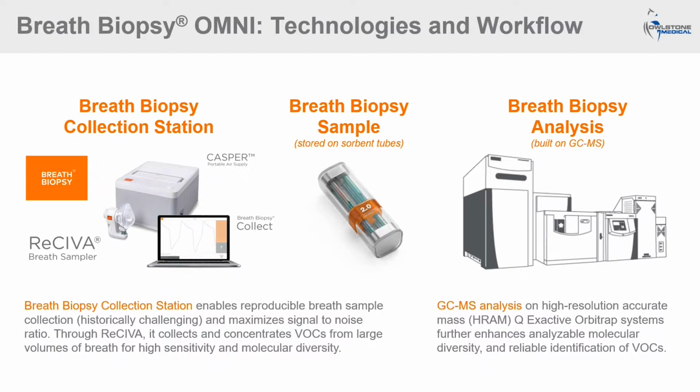Important to that whole setup is also the CASPER portable air supply. That is there to effectively filter out the VOCs that are present in the room where the sample is being collected, and it provides a filtered air supply into the ReCIVA. So the patient is actually breathing filtered air, and that could reduce a lot of the background false positives and false negatives that can come from the environmental air, typically in a normal breath workflow.